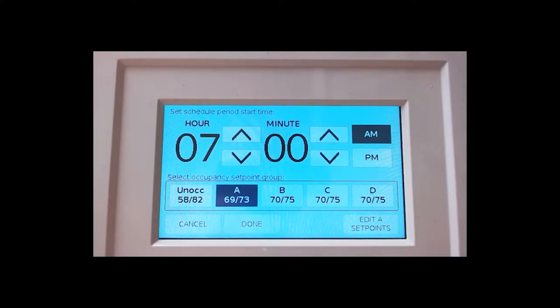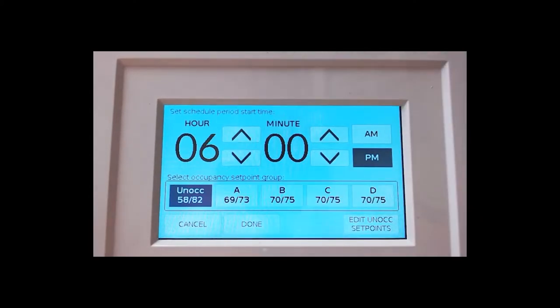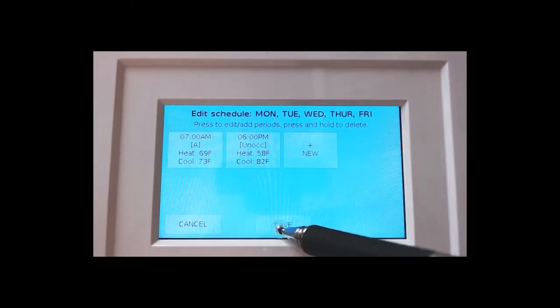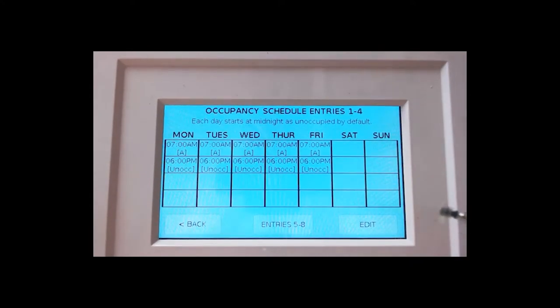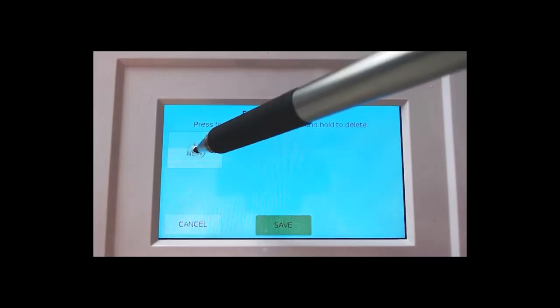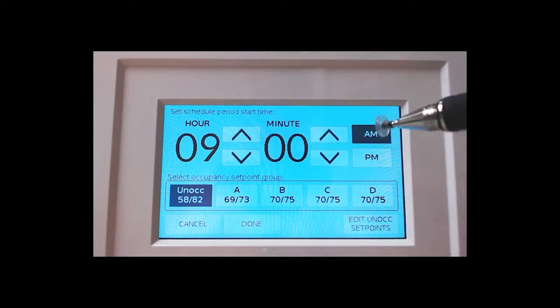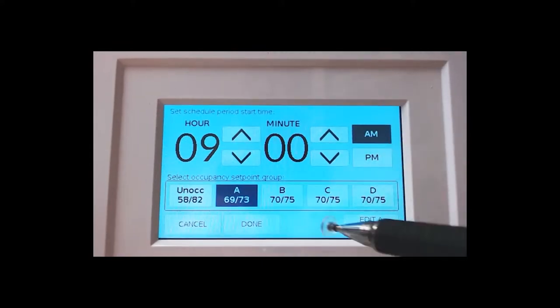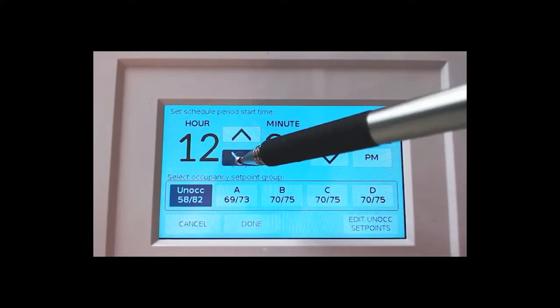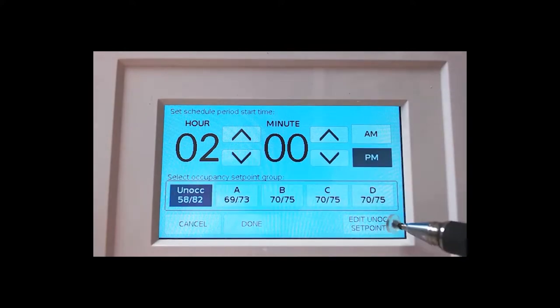So we're going to go ahead and save that by clicking done, and we want to extend these hours to 6 p.m. and use the unoccupied set point group. Okay, so now we've got our Monday through Friday schedule done, but we want to add some time on Saturday. So we're going to go ahead and click edit. We're going to select Saturday, and next we're going to add a new set point. We're going to have this start at, we'll say 9 a.m., and we're going to use the A set point group, and that's done. And then we're going to add another one for 2 p.m. and we'll use the unoccupied set point group at 2 p.m. and we're done there.